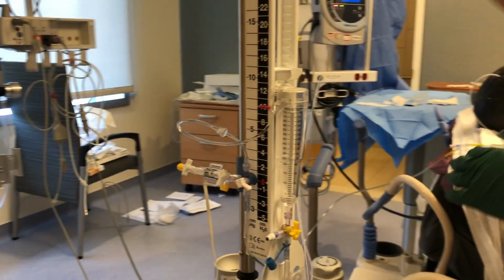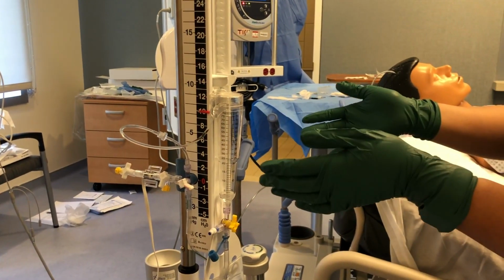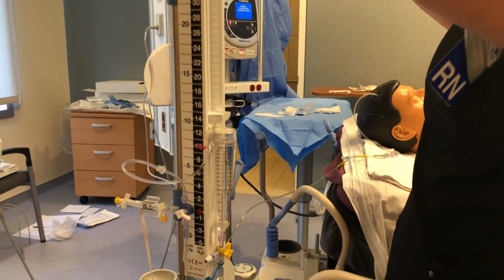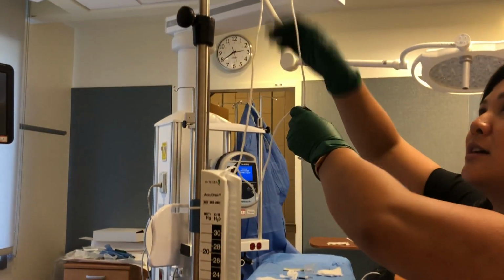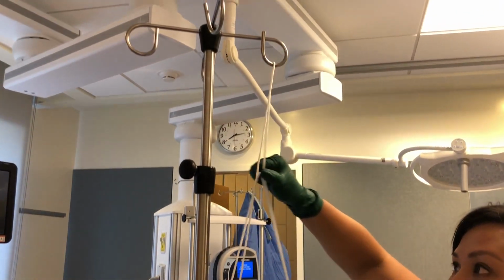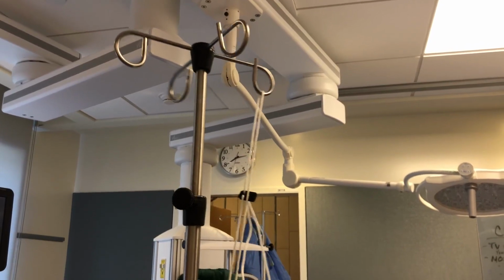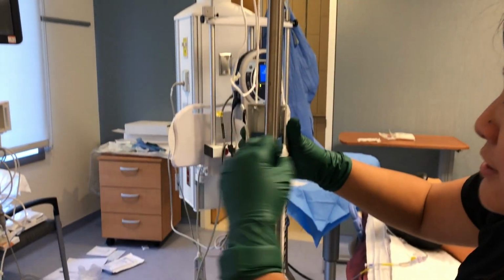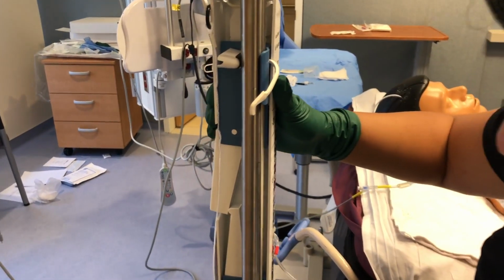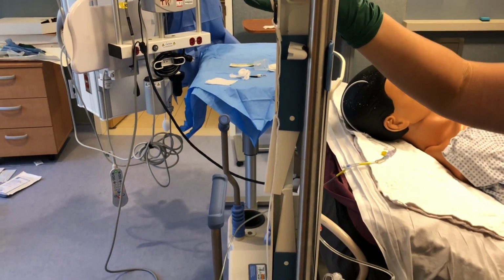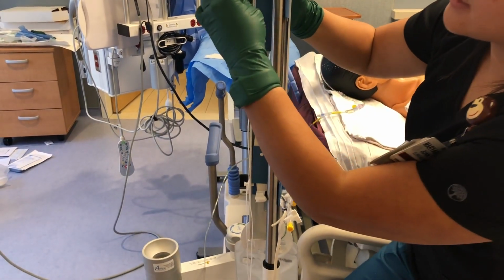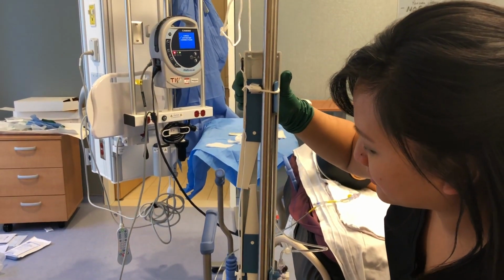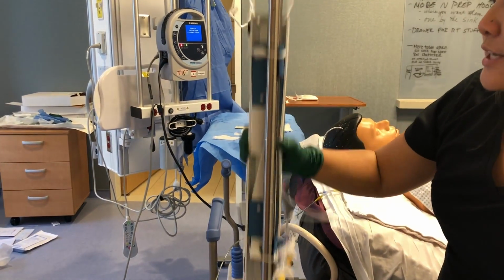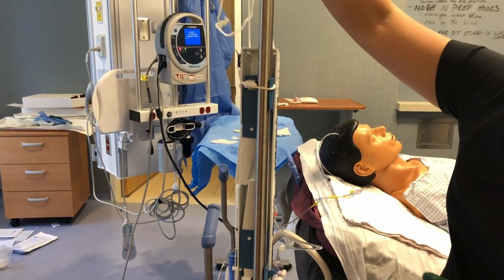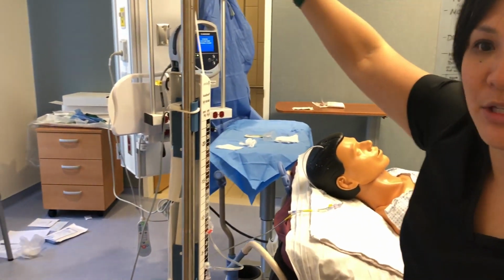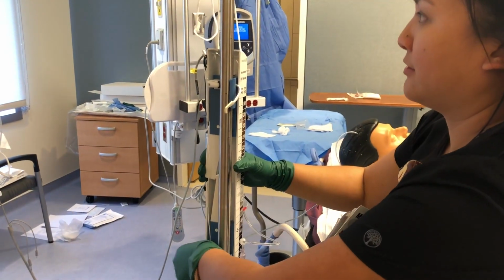So once you do have it leveled, you want to make sure that the AccuDrain is secure. So always have the string on to the IV pole and tighten it. And you also have in the back these rubber secures. So right now it's actually okay, but you want to make sure that it's still extra secure, so just re-snap it. You can still move the drain up or down, even with this secure system, but at least you also have this as a security system to make sure it doesn't completely fall to the floor.